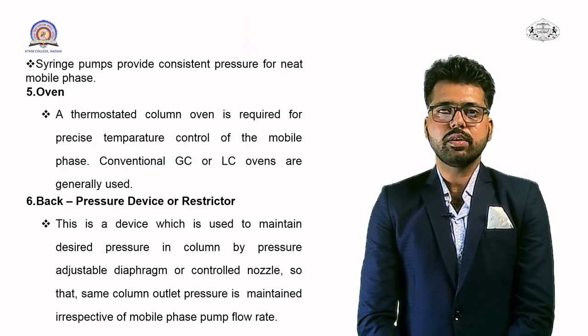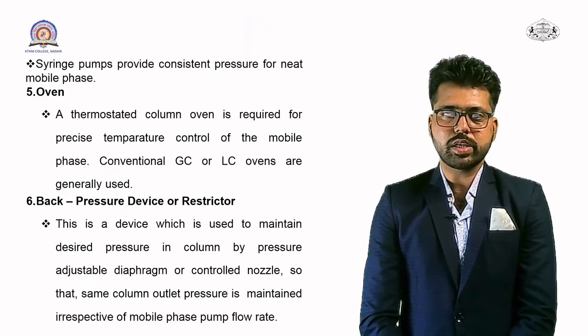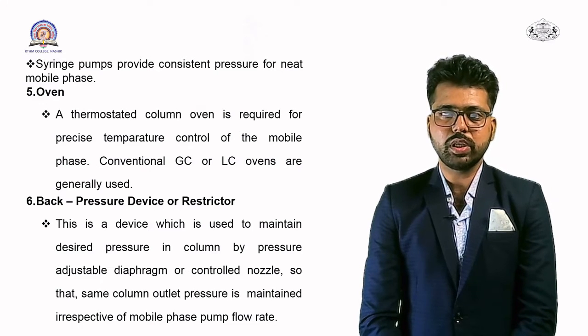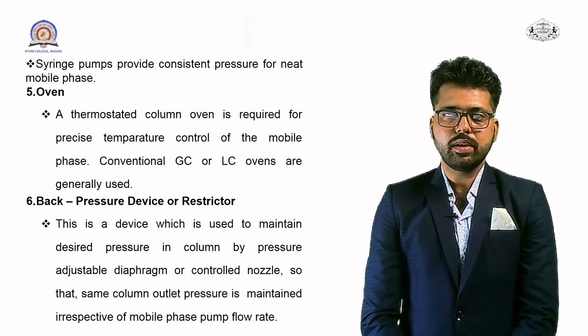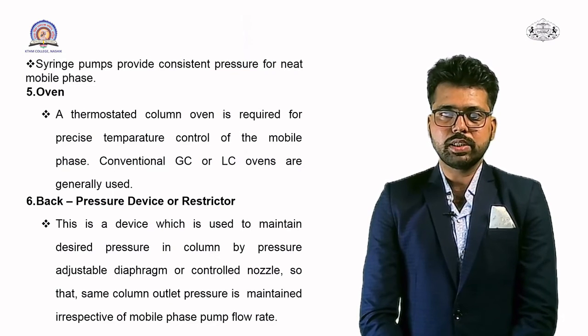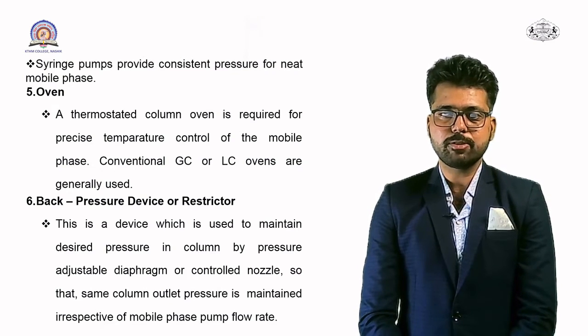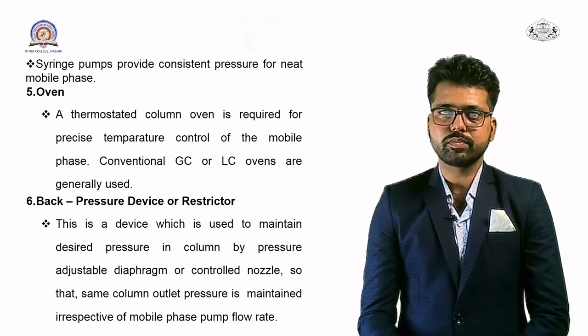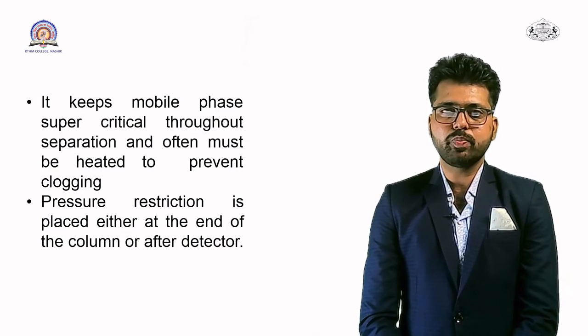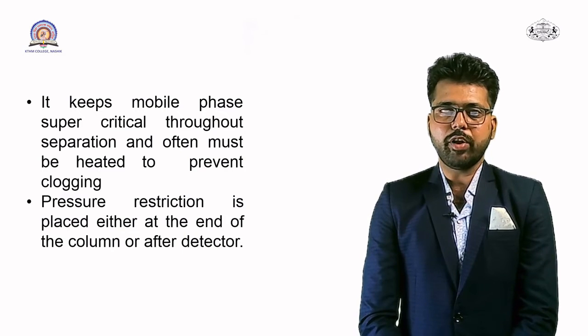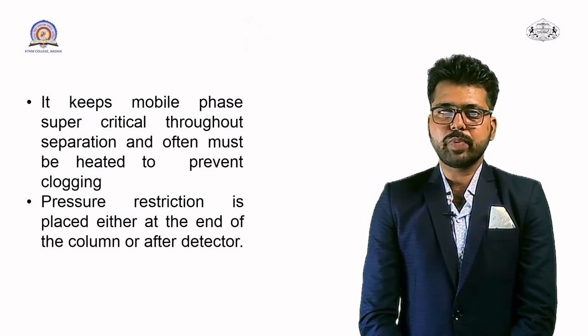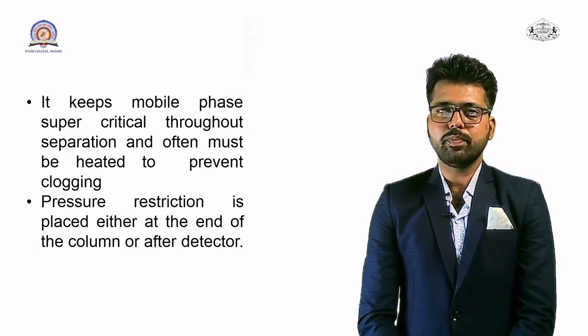Back pressure device or restrictor: This device is used to maintain the desired pressure in the column by a pressure-adjustable diaphragm or control nozzle, so that the same column outlet pressure is maintained irrespective of mobile phase pump flow rate. It keeps the mobile phase supercritical throughout separation and often must be heated to prevent clogging. Pressure restriction is placed either at the end of the column or after the detector.